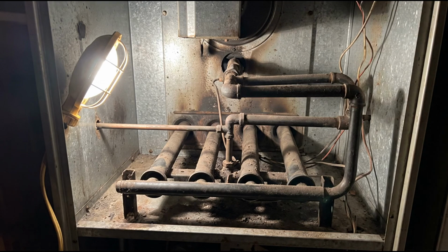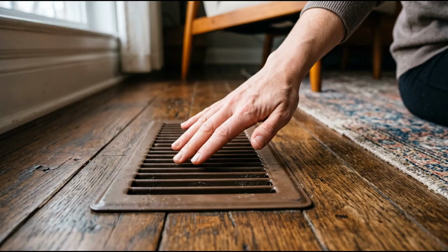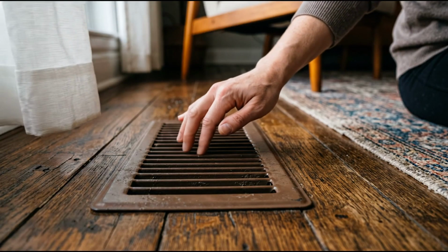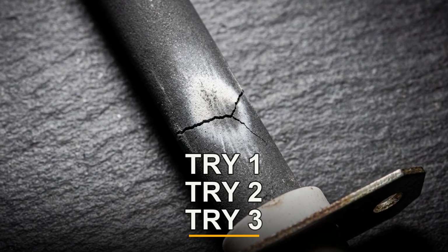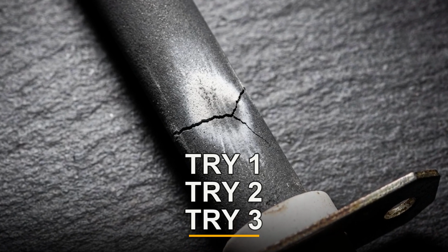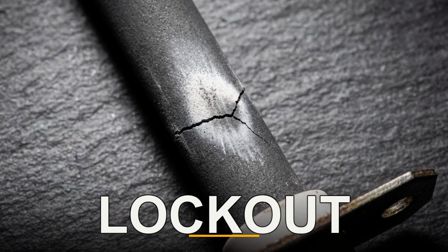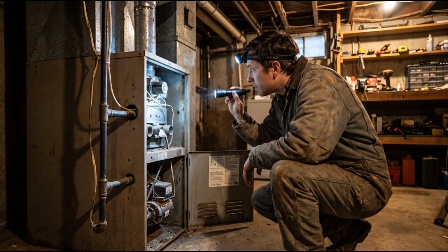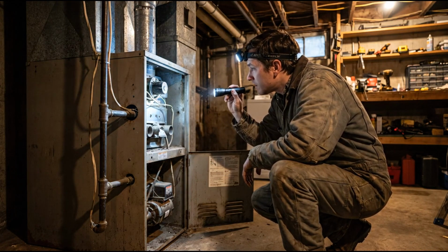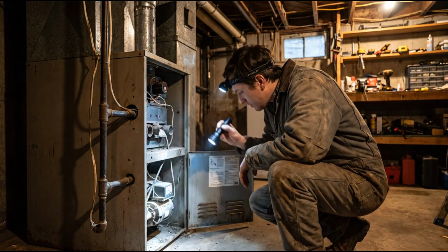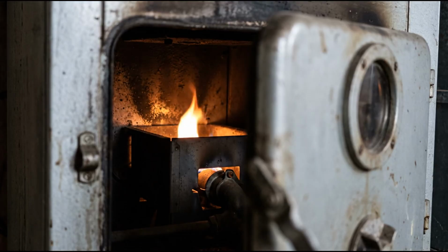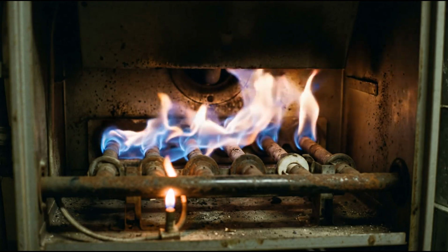Maybe a few minutes later, the blower runs anyway, and it is pushing cold air through the house. The furnace tries this 3, 4, 5 times, and then locks itself out. Now, go to the furnace and watch one attempt through the little sight glass with the lights off. In a healthy furnace, you will see an orange glow for 20 or 30 seconds before the flames come up.